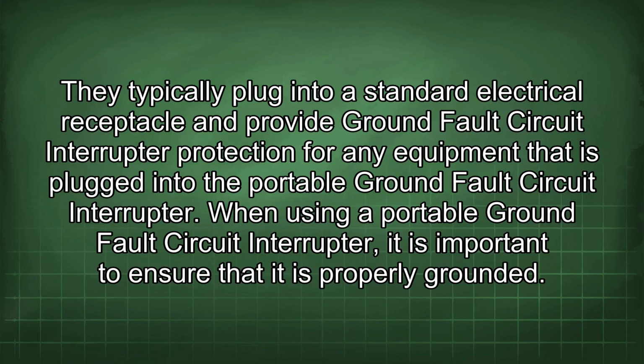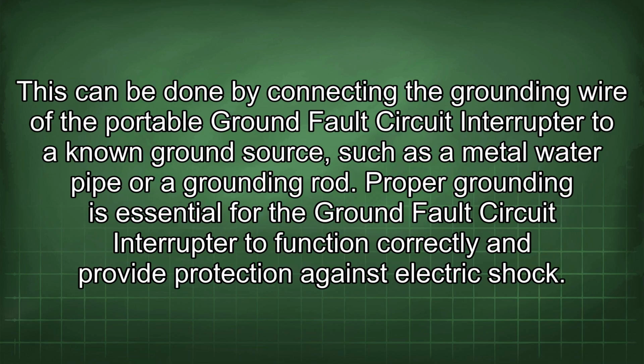When using a portable ground fault circuit interrupter, it is important to ensure that it is properly grounded. This can be done by connecting the grounding wire of the portable ground fault circuit interrupter to a known ground source, such as a metal water pipe or a grounding rod. Proper grounding is essential for the ground fault circuit interrupter to function correctly and provide protection against electric shock.